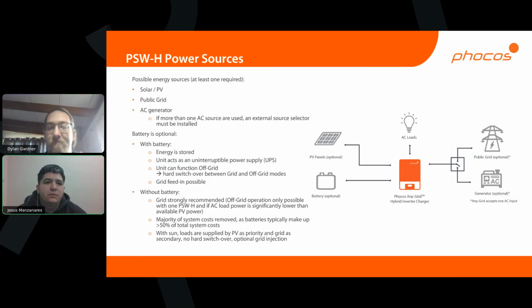Okay, so our energy sources going to the inverter. Like I've said before, if you want to be completely off grid, all you would need is properly sized panels and batteries to provide a full off grid solution with no public grid or generators. You can have each one of these separately: a PV and battery only case, or public grid and battery only, using the battery as a full backup in case your grid ever goes out.